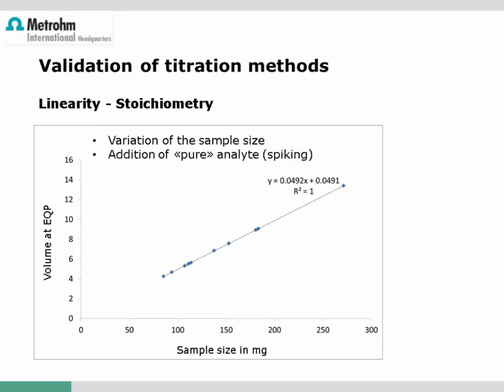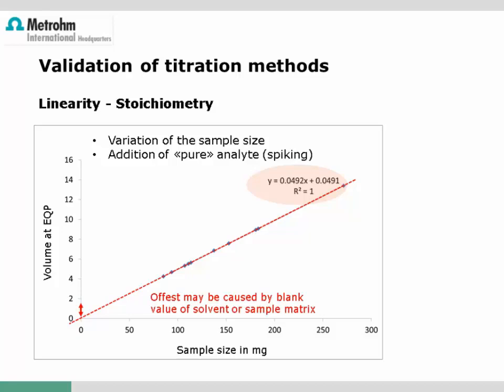For validation of the designated application, the same procedure may be applied: several different sample sizes are titrated and the recovery is calculated. Important is also checking linearity — the volumes at the equivalence points for different sample sizes should be on a straight line with a good regression factor, and extrapolation to zero sample should exactly cross the zero point of both axes. If this is not the case, either the stoichiometry of the chemical reaction is not the same for all sample sizes, or the sample matrix or solvent shows a blank value, which would then have to be considered for each titration.